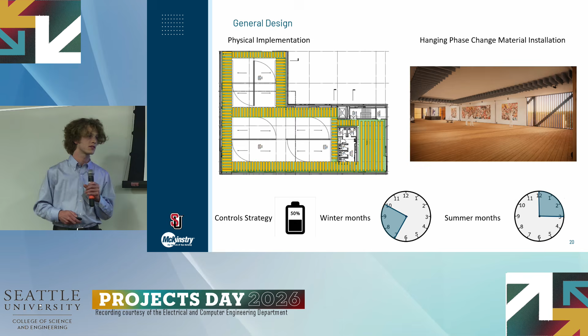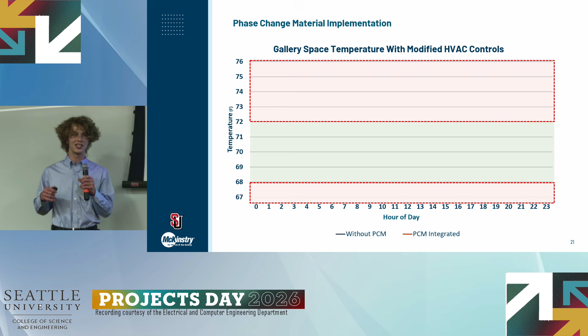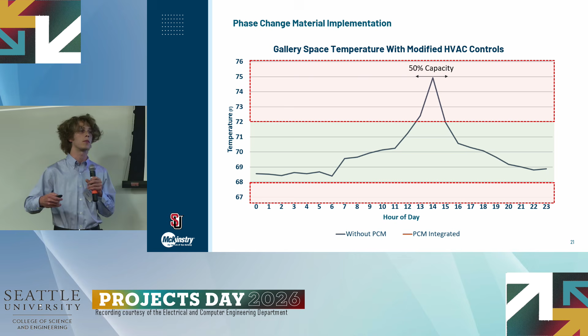Now, in order for the strategy to be valid, we must maintain those stringent gallery temperature requirements. As a reminder, this is 70 degrees plus or minus 2 degrees Fahrenheit, shown in this green section. Without any PCMs integrated during that 50% reduction period, the temperature falls out of this range, meaning that the artwork is compromised. With PCMs integrated, this temperature is maintained, protecting the artwork.